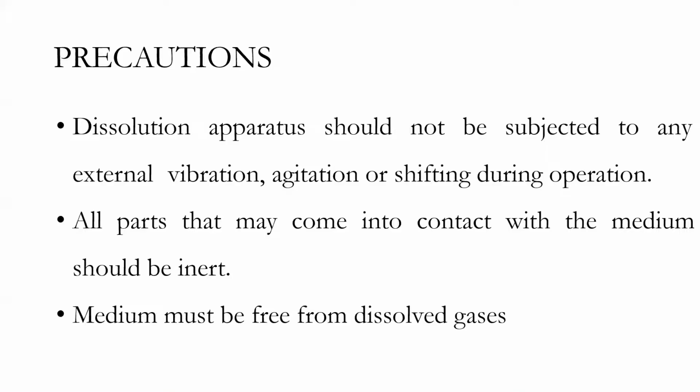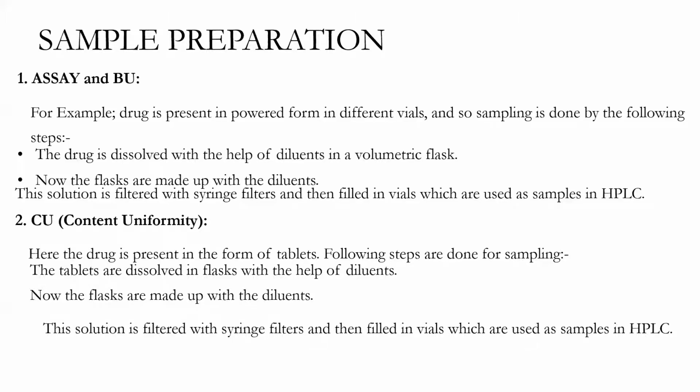So some precautions must be taken. The dissolution apparatus should not be subjected to any external vibration or agitation during this operation. It should not be shifted from one place to another during the operation. All the parts that may come into contact with the medium should be inert, and the medium must be free of dissolved gases.